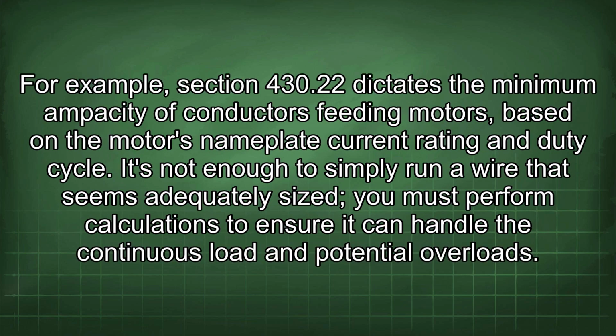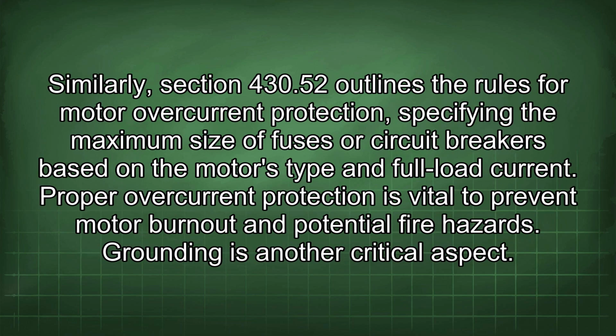For example, Section 430.22 dictates the minimum ampacity of conductors feeding motors, based on the motor's nameplate current rating and duty cycle. It's not enough to simply run a wire that seems adequately sized. You must perform calculations to ensure it can handle the continuous load and potential overloads. Similarly, Section 430.52 outlines the rules for motor overcurrent protection, specifying the maximum size of fuses or circuit breakers based on the motor's type and full load current. Proper overcurrent protection is vital to prevent motor burnout and potential fire hazards.